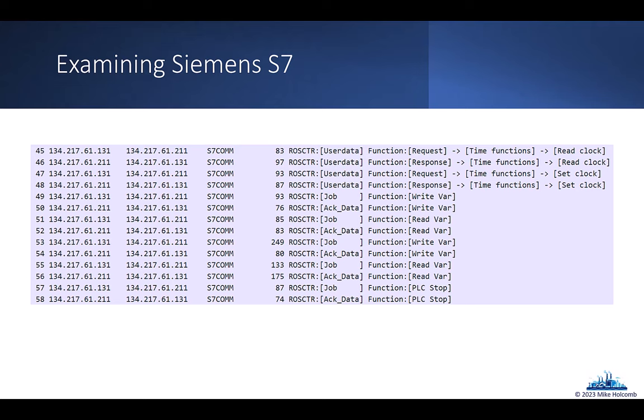Now, the one kicker with this example, when I started looking at it, the first thing that jumped out is the IP addresses. These are public IP addresses. These are hosts on the internet. These are not internal, not private IP addresses. So, as you'd imagine, this would indicate traffic over the internet, which is more than likely. Now, you can actually use public IP addresses internally and still have it private, but on the surface this would look like two hosts communicating over the internet. We never want our OT assets exposed to the internet, not directly, because that's going to leave them open and vulnerable to attack, right? But this is what it looks like through Wireshark.